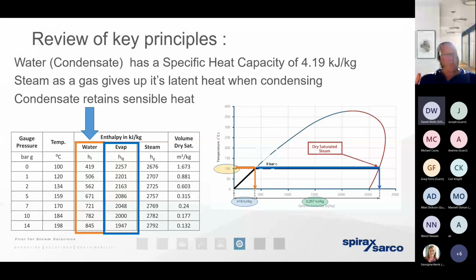But what you'll remember is it's the box highlighted in blue that demonstrates the useful energy content of the steam. So that's the information we use to size the heat exchanger or size the requirement of the process. And you'll notice there's more useful heat energy in steam at a lower pressure than there is at a higher pressure. So that's another reason why we want to reduce the pressure of the steam as low as we possibly can at the point of use, to ensure it's operating with maximum efficiency.